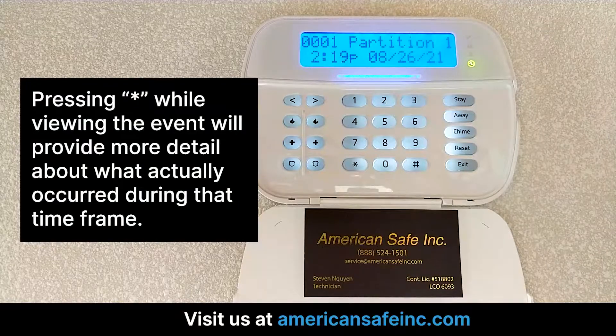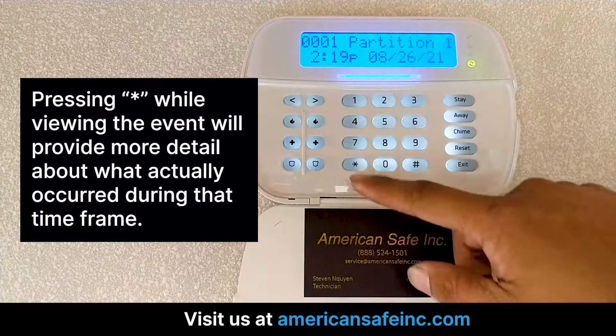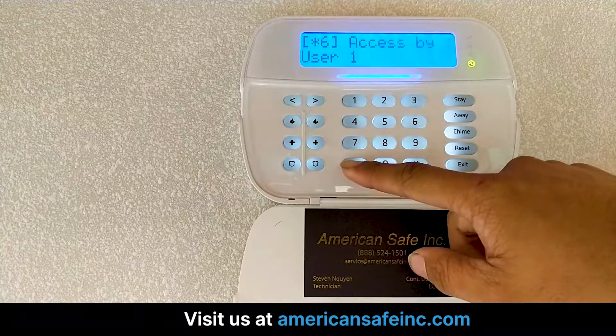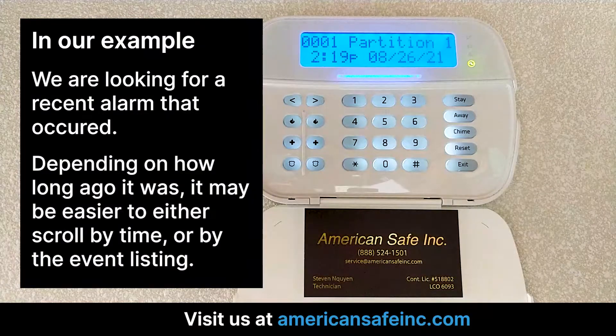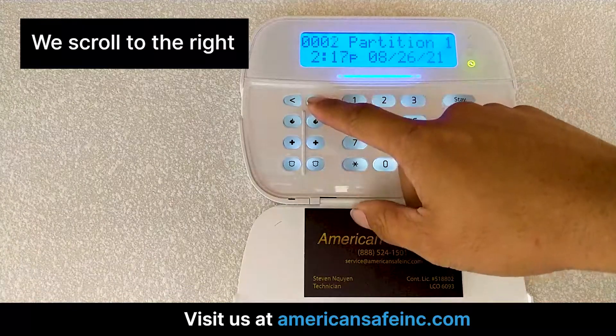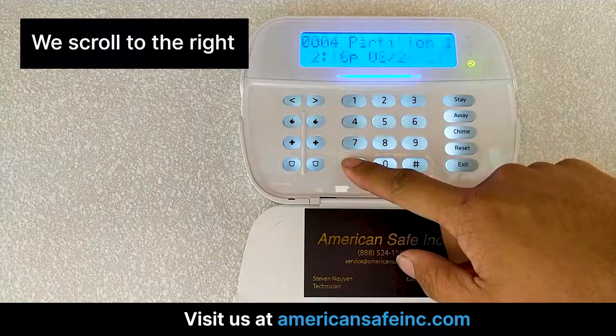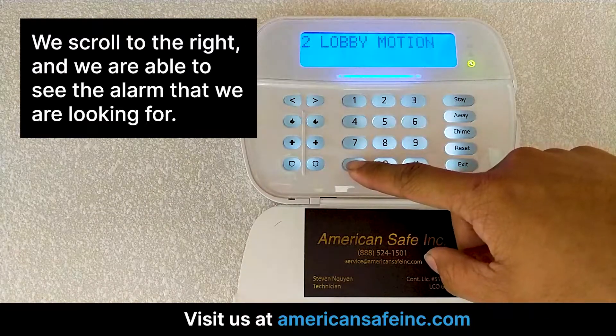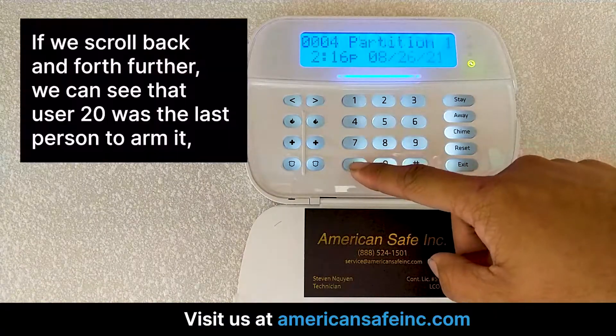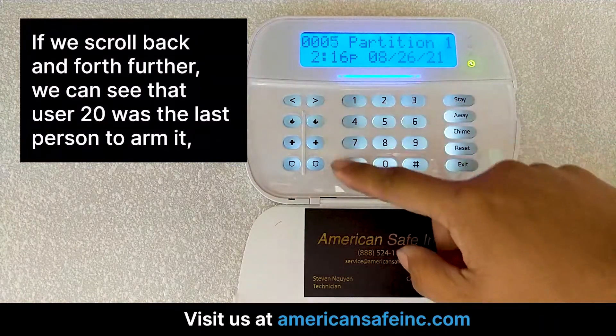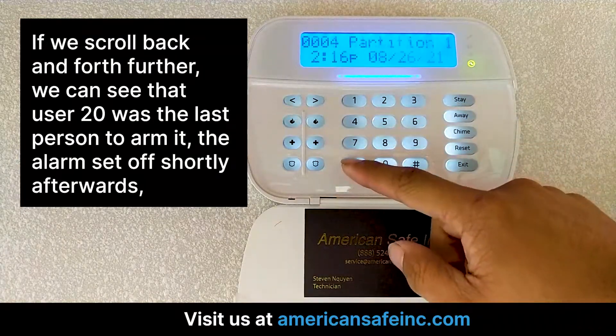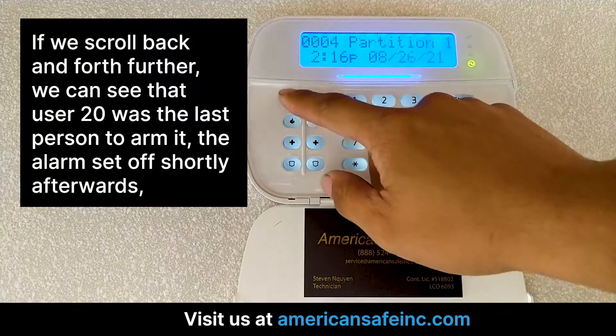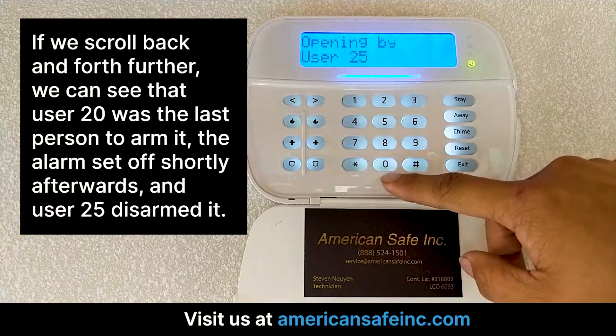Pressing star while viewing an event will provide more detail about what actually occurred during that timeframe. In our example, we are looking for a recent alarm that occurred. Depending on how long ago it was, it may be easy to either scroll by time or by the event listing. We scroll to the right and are able to see the alarm we were looking for. Scrolling back and forth further, we can see that user 20 was the last person to arm it, the alarm set off shortly afterwards, and then user 25 disarmed it.